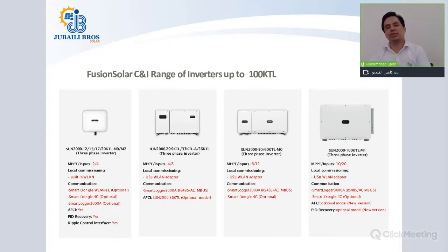So now I just want you guys to focus on these local commissioning device and communication, because when I will be speaking in my next slide about the application scenarios, I will be bringing your attention to these 2 points again, which is the local commissioning and the remote communication. So for the 12 to 20 kilowatt, the local commissioning is the built-in Wi-Fi. So you do not need any external device. It is the built-in Wi-Fi inside the inverter, which you can use to commission the inverter. For the remote communication, these inverters can communicate through the dongle WLAN, which is a Wi-Fi device, and also this device has the fast Ethernet communication option. So either of the two can be used.